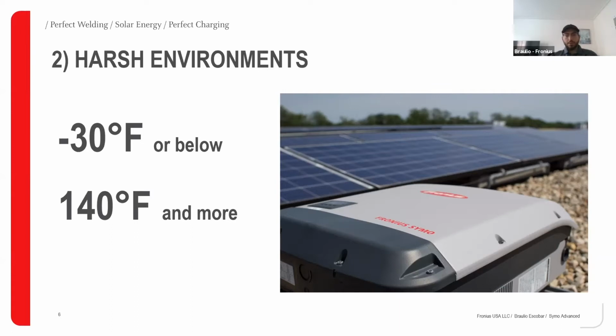While it's commonly known that higher temperatures impact the efficiency of solar modules, the impact on inverters is often overlooked. Even in temperate climates, commercial rooftops can quickly reach temperatures of 140 degrees. Power electronics in the inverter automatically derate as a protective measure when temperatures are too high or too low, affecting the overall system yield.